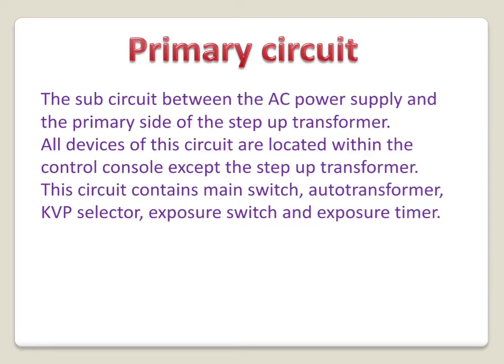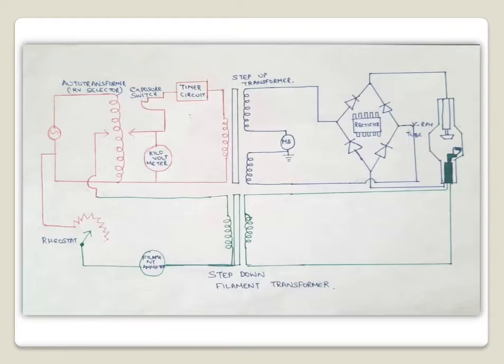In the primary circuit you will find devices such as the main switch, the auto transformer, KVP selector, exposure switch, and exposure timer. All these parts are present inside the operating console, except the primary coil of the step-up transformer which is present outside the operating console. So the primary circuit extends between the source of alternating current up to the primary coil of the step-up transformer.